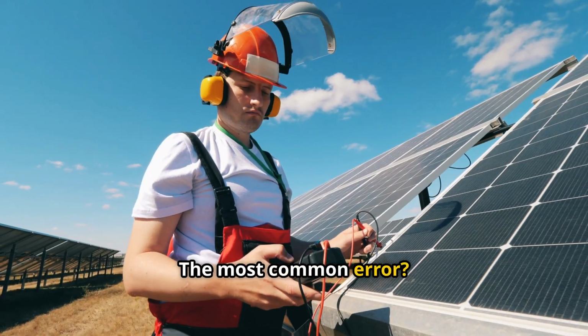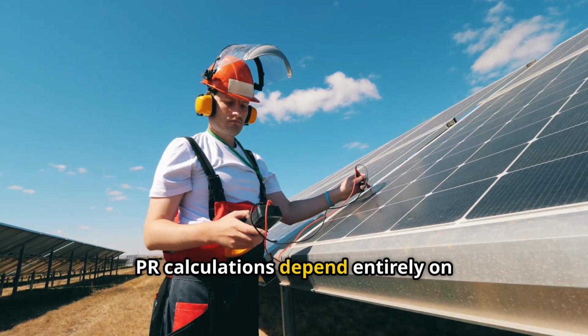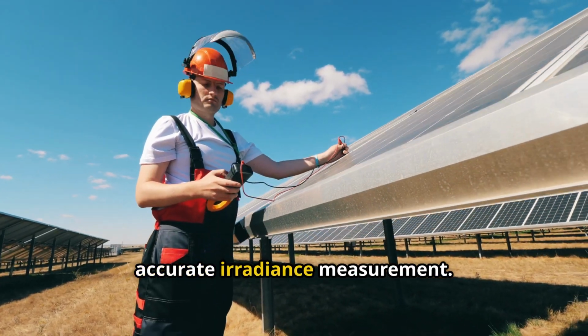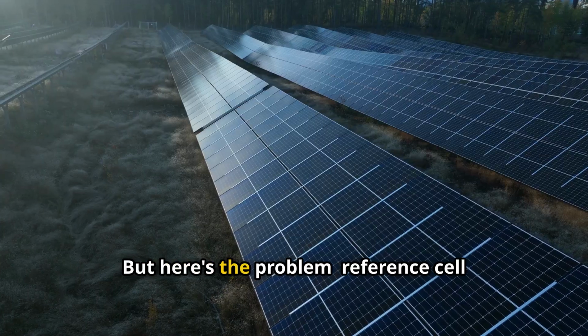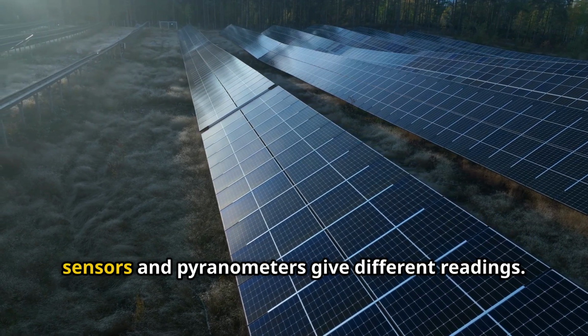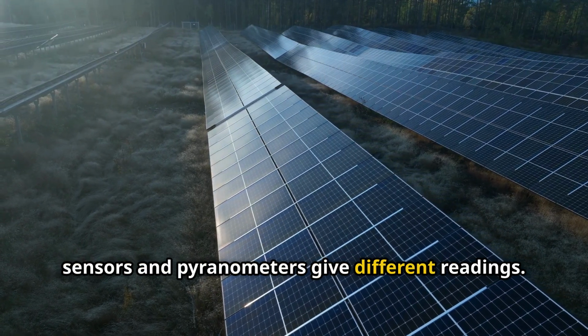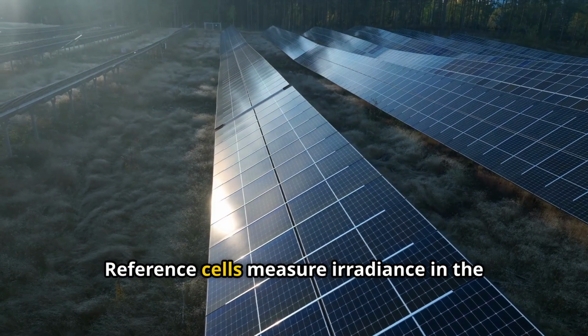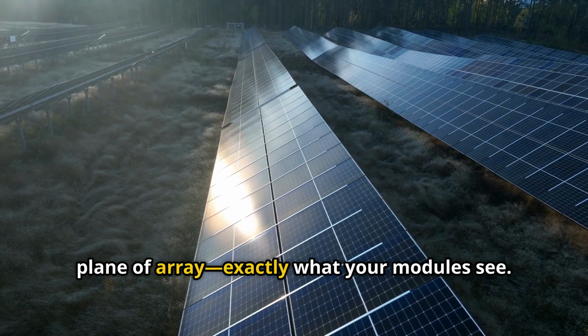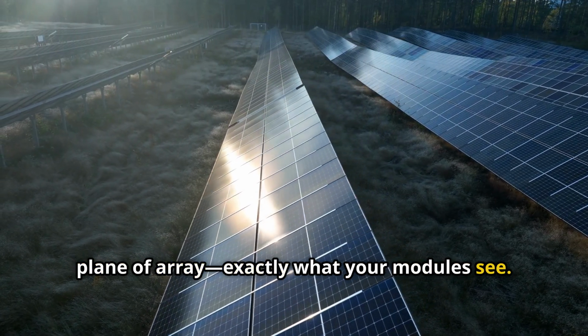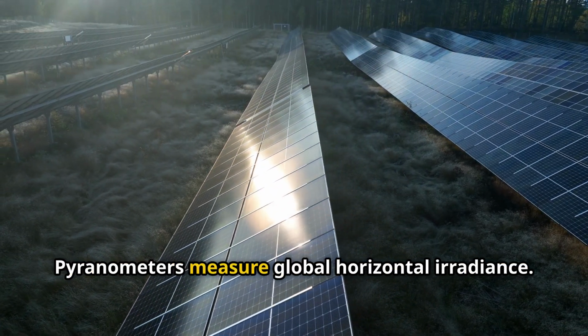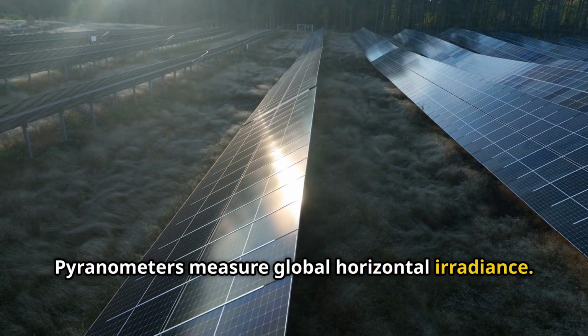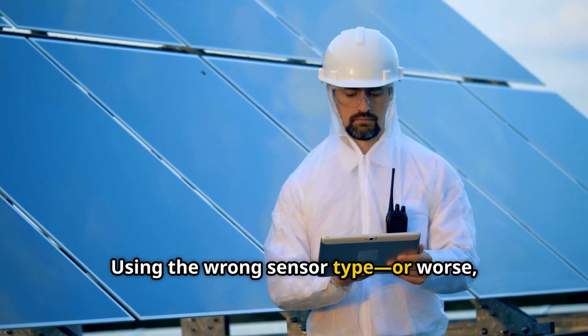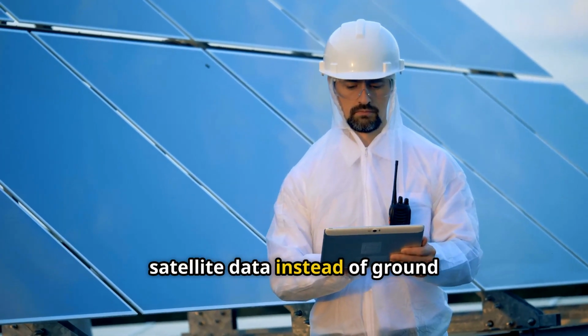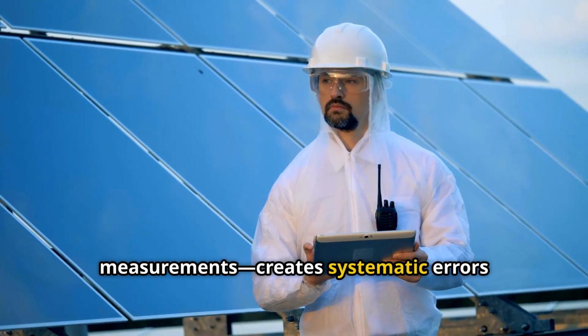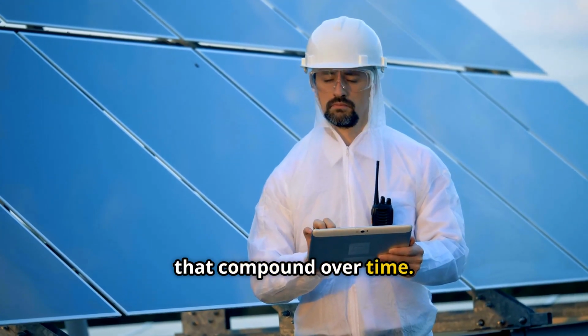The most common error? PR calculations depend entirely on accurate irradiance measurement. But here's the problem. Reference cell sensors and pyranometers give different readings. Reference cells measure irradiance in the plane of array, exactly what your modules see. Pyranometers measure global horizontal irradiance. Using the wrong sensor type, or worse, satellite data instead of ground measurements, creates systematic errors that compound over time.